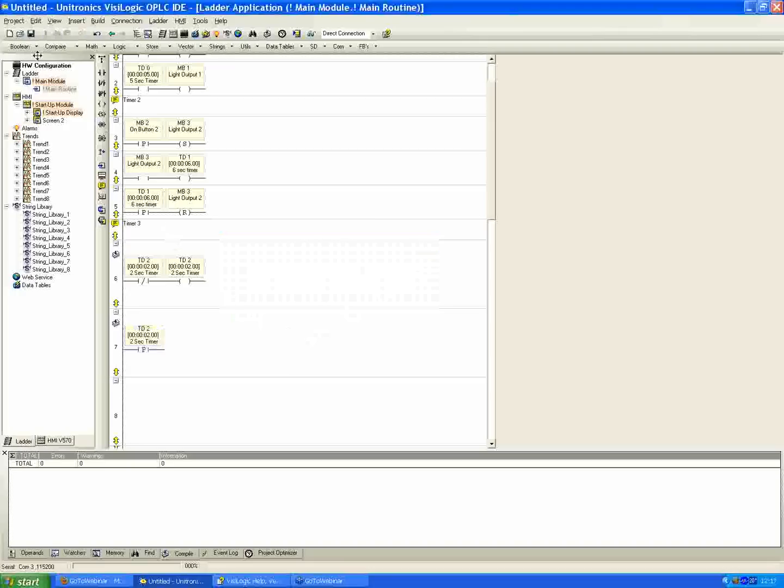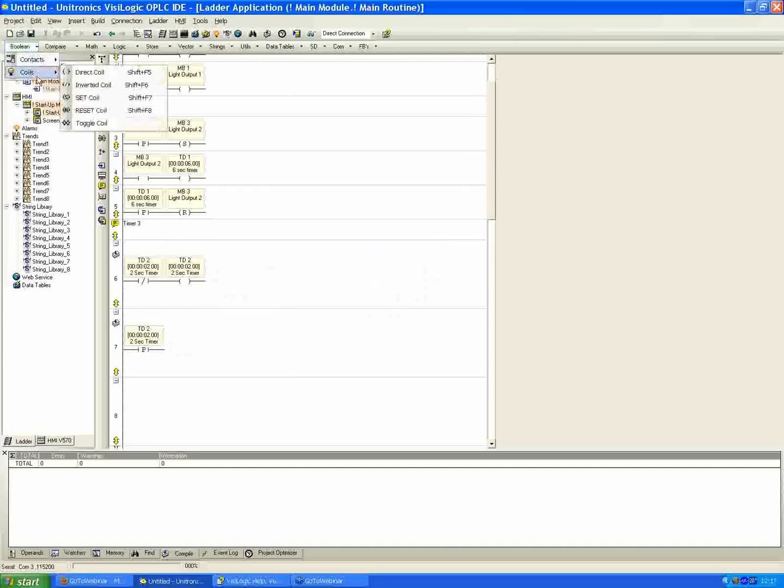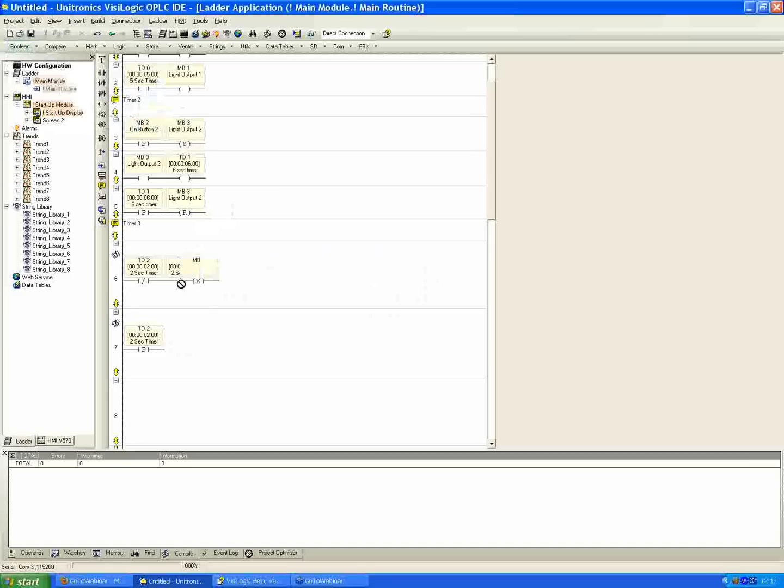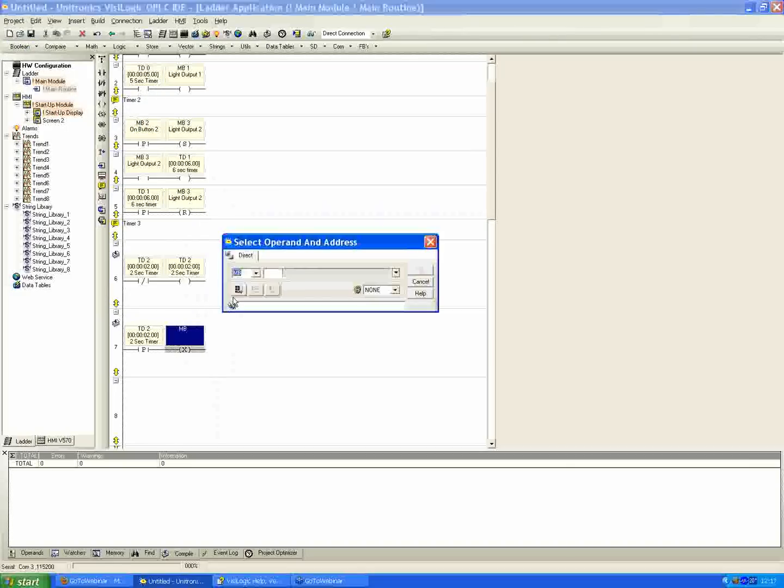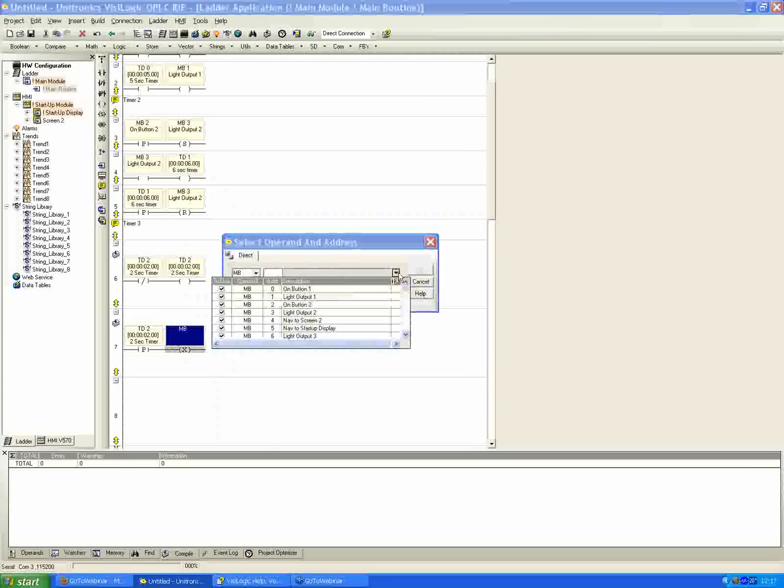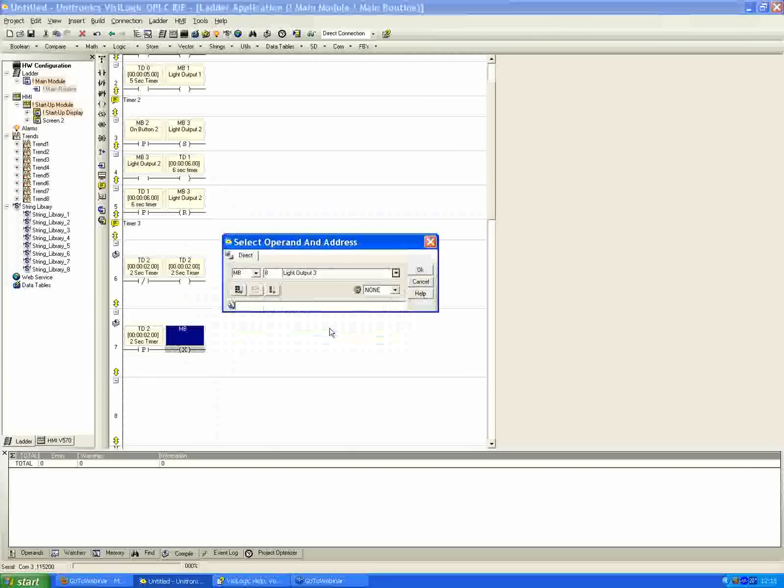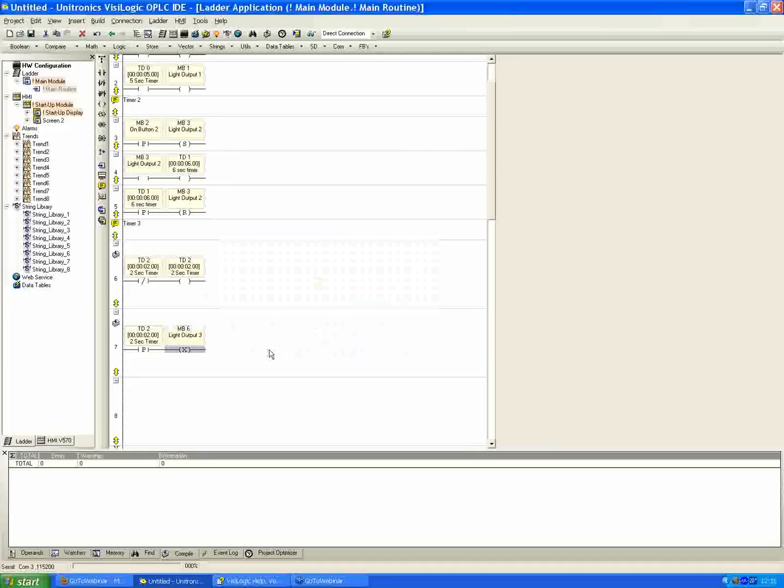Now we'll use, in this case, a different type of coil. If you go to the Boolean menu, and then coils, we've used, or we've talked about most of these before. Direct inverted is just the opposite of direct. Set and reset we looked at previously. The last option is toggle coil. I'm going to select that and place it in series with net 7. And in this case, I'm going to select my light output 3 and hit OK.